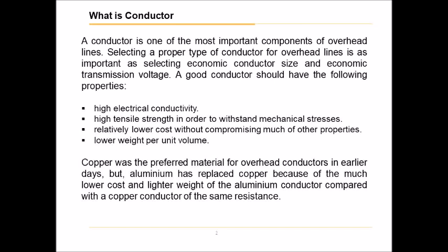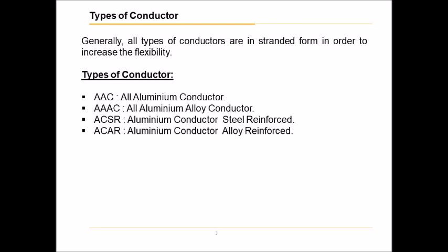Copper was the preferred material for overhead conductors in earlier days, but aluminium has replaced copper because of the much lower cost and lighter weight of the aluminium conductor compared with a copper conductor of the same resistance. Generally, all types of conductors are in stranded form in order to increase flexibility.